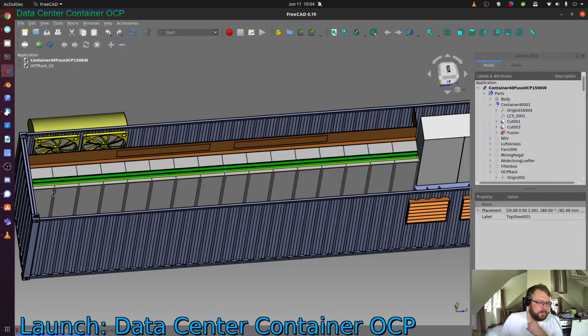As I said, we have 16 racks internal here. An OCP rack is different from standard equipment because the temperatures and the energy density go up relatively high — up to an average of 15 kilowatts, max up to 20 kilowatts. So this data center is now planned for 150 kilowatts, which is actually low — in standard use cases, the power can increase up to 200 kilowatts.